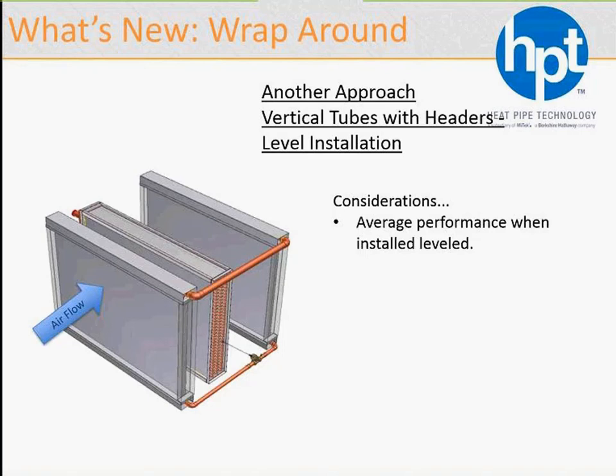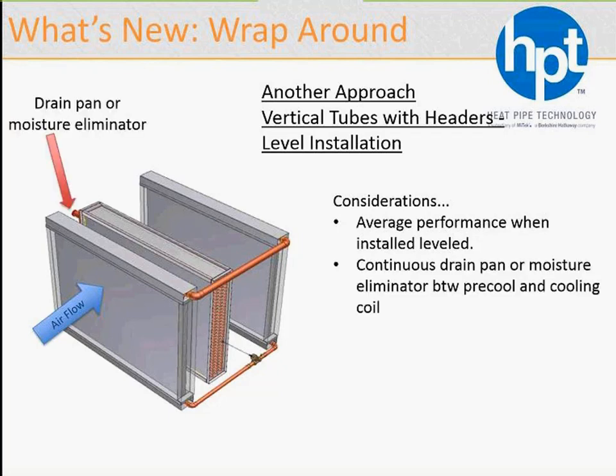There are some considerations for this product. Performance is about average, lower than our standard, and we'll show you another iteration of this product where performance is actually quite enhanced. Because of the fins being horizontal, a continuous drain pan will be needed to capture condensate that tends to blow off from the pre-cool heat pipe downstream in the direction of airflow. So if an extended drain pan is not available, moisture eliminators may be needed. And because of the nature of this product, air profile is not quite uniform. Air blenders will be needed downstream of the reheat heat pipe.